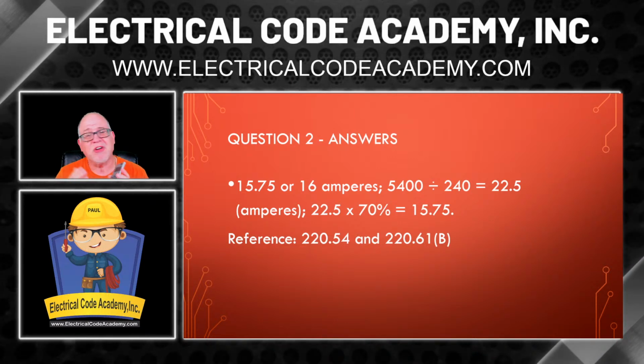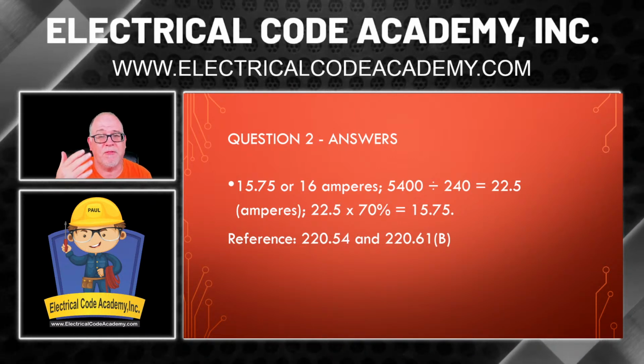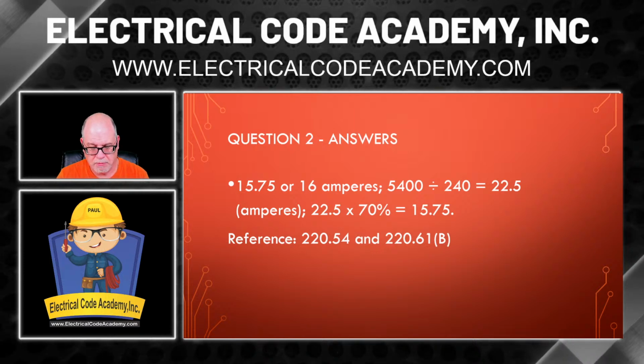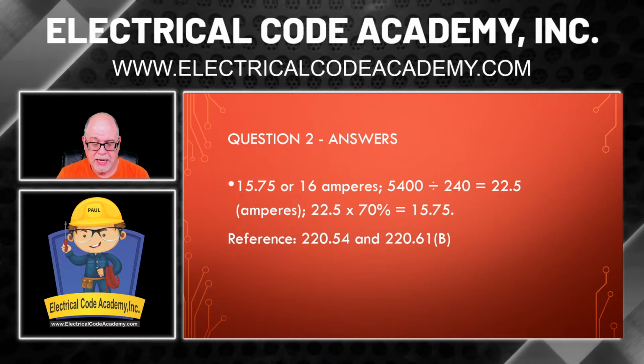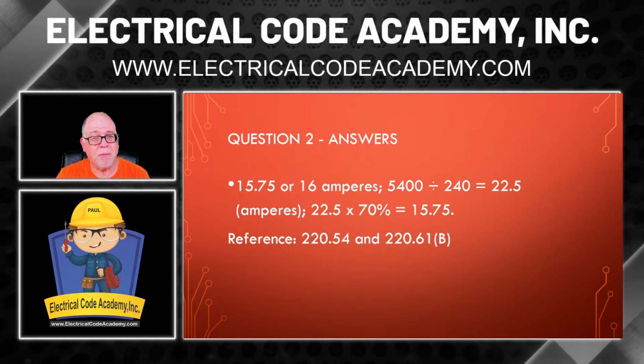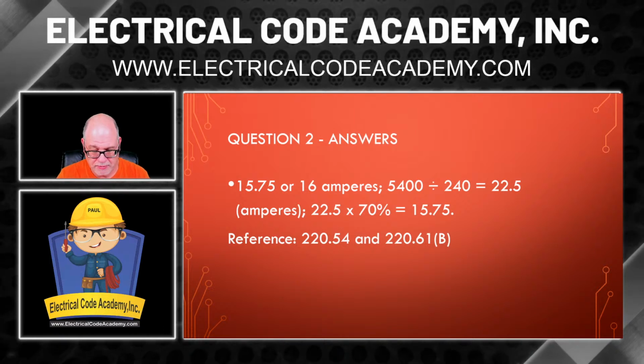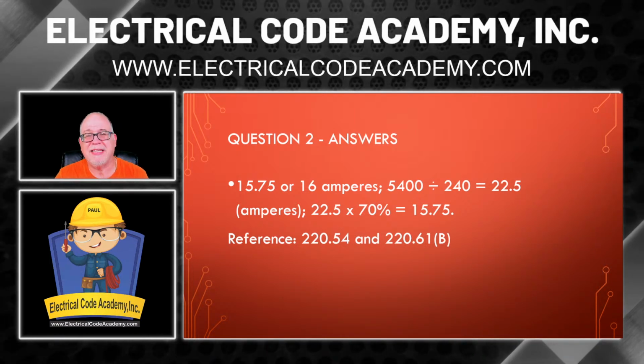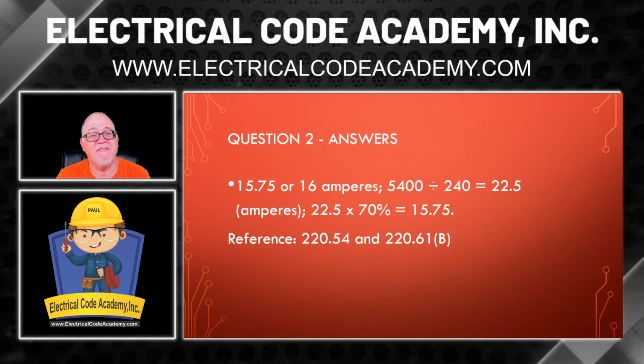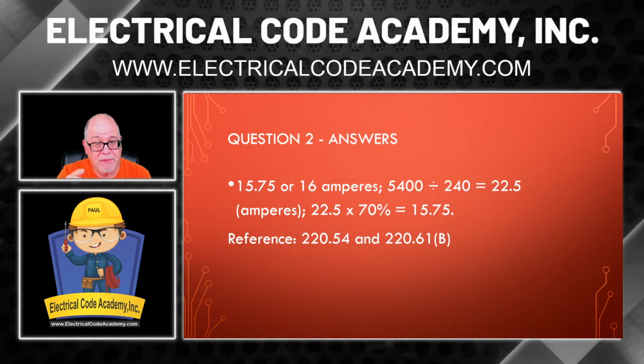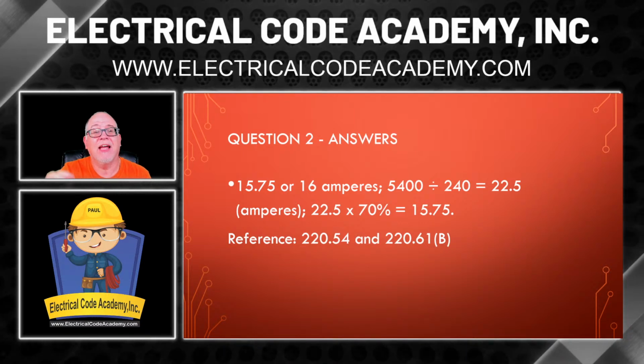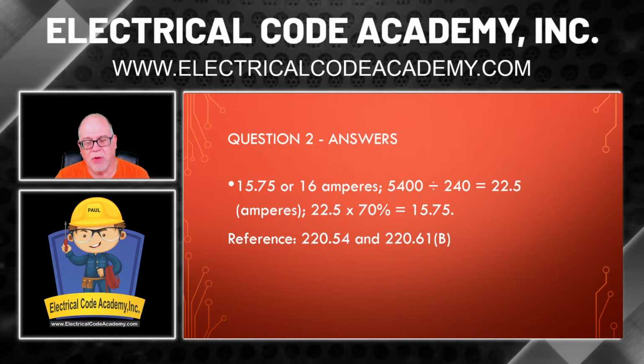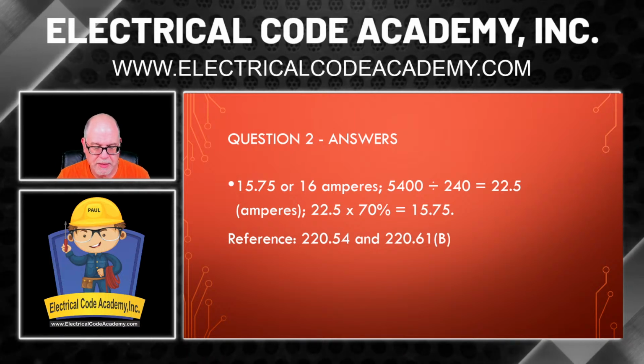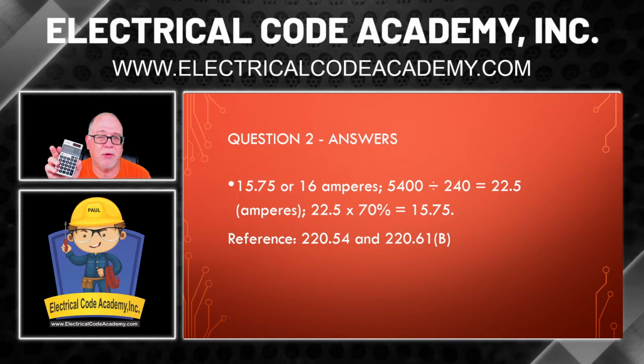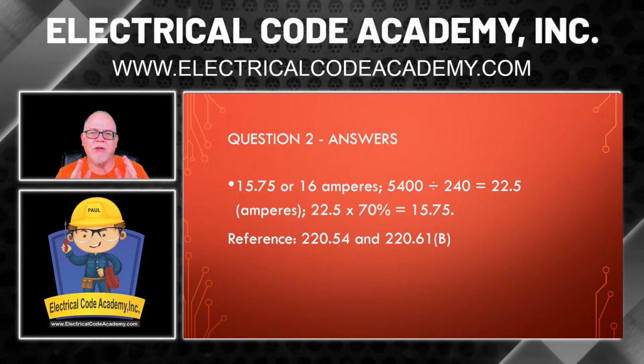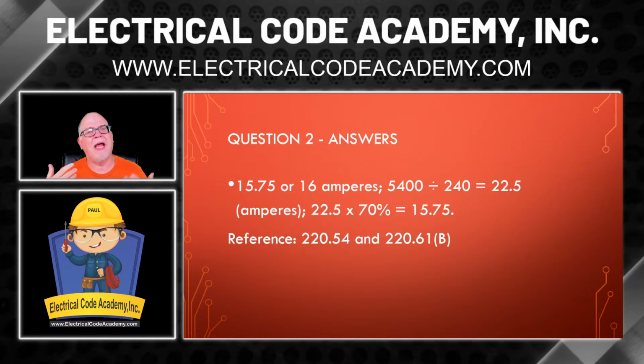So one other way you could have done this is start with our full value, our 5,400, right? 5,400, and you could have done what? Multiplied that by 70%. And that gives you 3,780 VA. Then you could take that and divide that by 240 volts. So divide that by 240. And that also gives you 15.75. Always remember, there are many ways that you can do this.